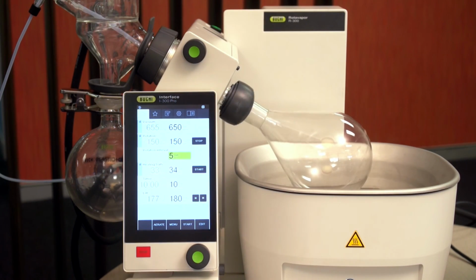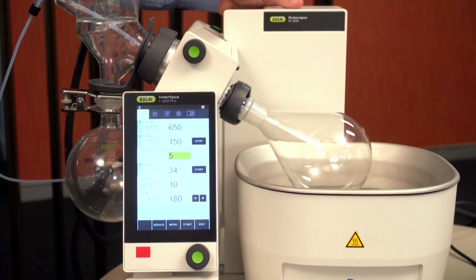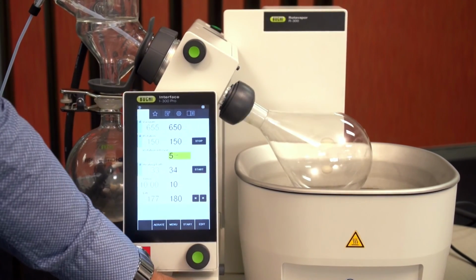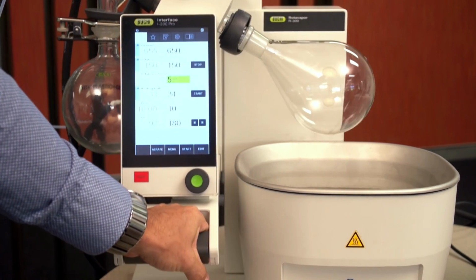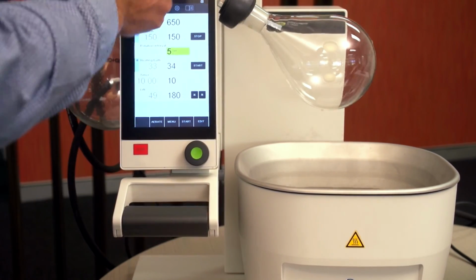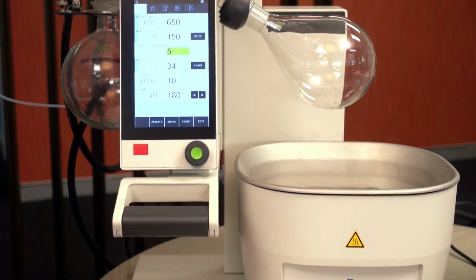Once our distillation is finished, because we have the electronic version of the Buchi Rotavapor R-300, we're using the handle here and we simply pull back, and the electronic lift takes it up nicely for us. We can hit stop on the rotation and we're finished. So that's it. Thank you very much for watching.